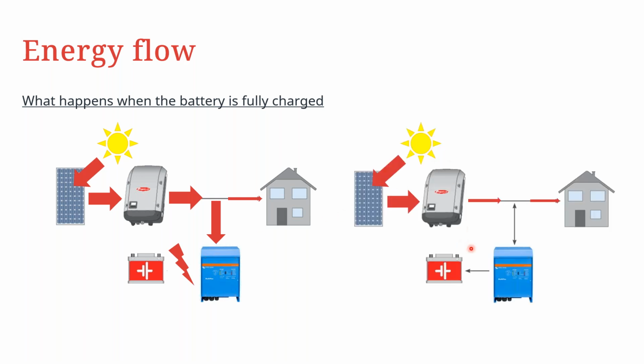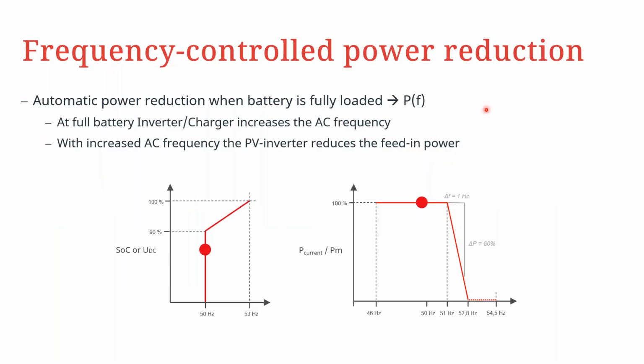So what needs to happen is that there needs to be some form of communication from the battery inverter to the Fronius inverter to tell the Fronius inverter that although we have very high production by the solar panels, we only need a certain amount of power in the network. And therefore, this is what we are referring to as the frequency drop communication between the Fronius and the Victron inverter. And therefore, there is an automatic power reduction when the battery is fully charged.